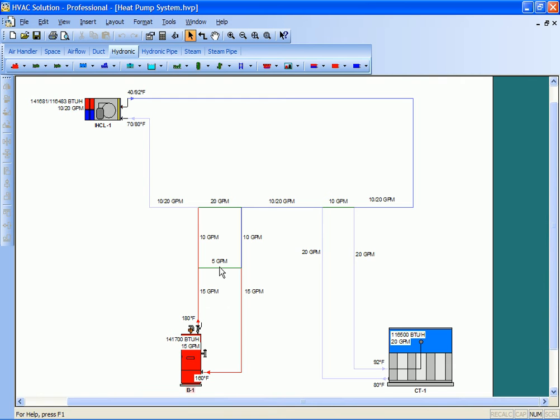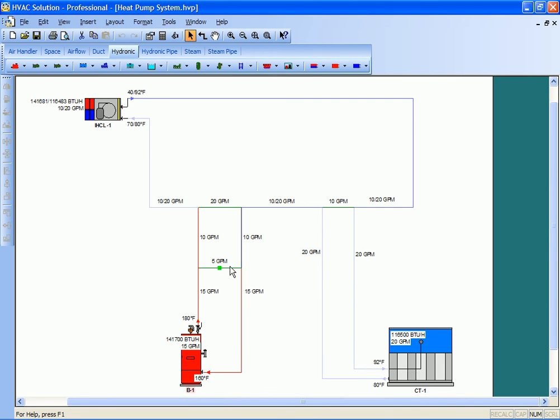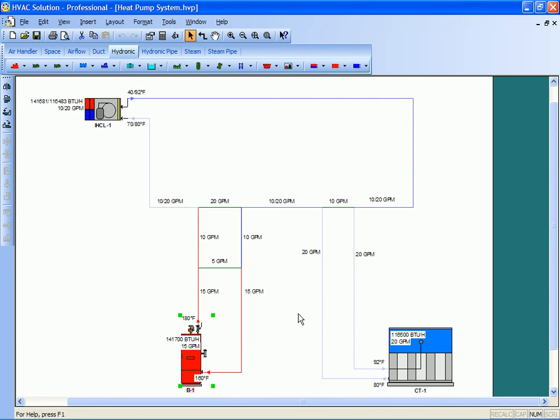One trick here is we want this boiler injecting. To do that, I need to put a flow direction right here in this bottom loop, and the final thing that I need to do is in the boiler, I need to make sure that I define both temperatures so that I force a flow.